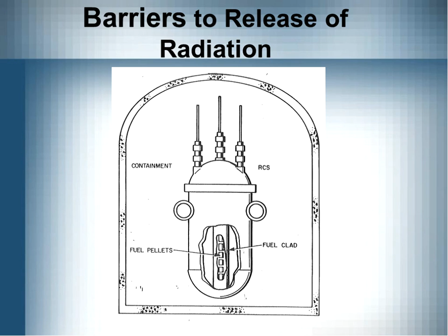Now, for these isolation valves, there's always redundancy in them. And like I said, there's 2 valves for every line. One of them may be powered by an AC motor. The other one in that line would be powered by a DC motor. So they're always powered. If it's powered by something other than electricity, it can be a fail-safe form. It can be an air-operated cylinder that would open the valve. Those are all spring-loaded. Basically, in an accident signal, all the valves on containment are designed to keep everything within the containment.